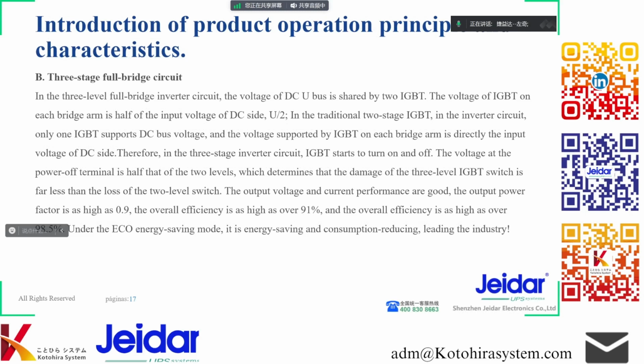Three-level full-bridge inverter circuit. In the three-level full-bridge inverter circuit, the voltage of the DC bus is shared by two IGBTs. The voltage of the IGBT on each bridge arm is half of the input voltage of the DC side. In the traditional two-level IGBT inverter circuit, only one IGBT supports the DC bus voltage, and the voltage supported by the IGBT on each bridge arm is directly the input voltage of the DC side.